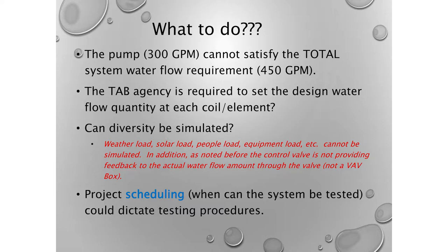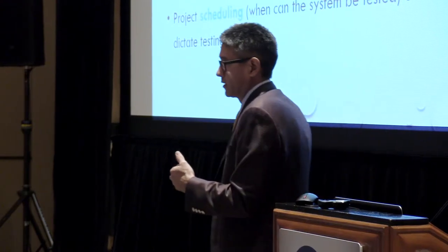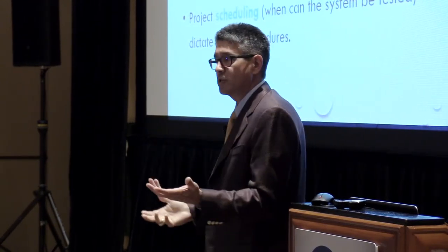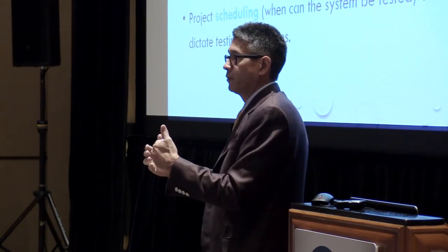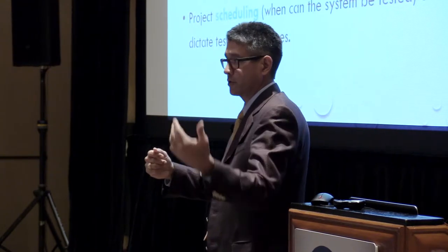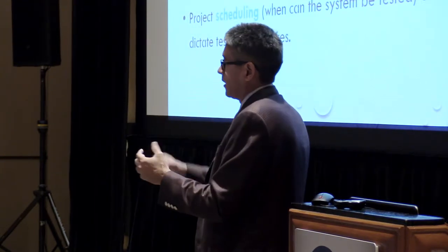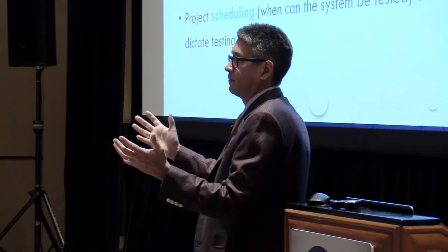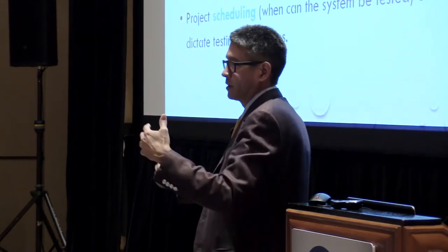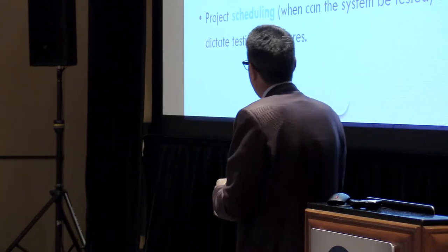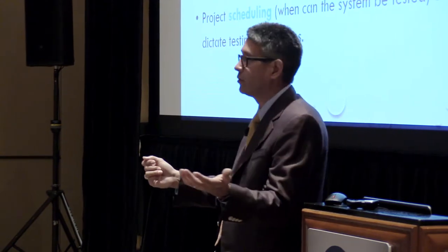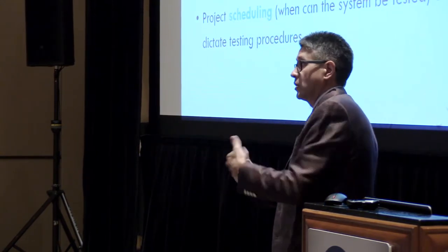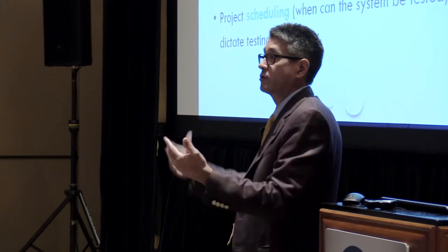So we're going to go through and sit there and say, one, can diversity be simulated? Trying to simulate diversity becomes a challenge. And when you start doing that, what are you going to do when you're setting up your different valves for different scenarios? So if you set it up and you say, I'm going to blow open 50% of the valves to 100% and simulate a west exposure, once you set those valves, you're setting that one condition. You cannot redo it now. Or you can redo it, change your valve positions. Now you can find you might be short in some areas, overflowing in other areas.